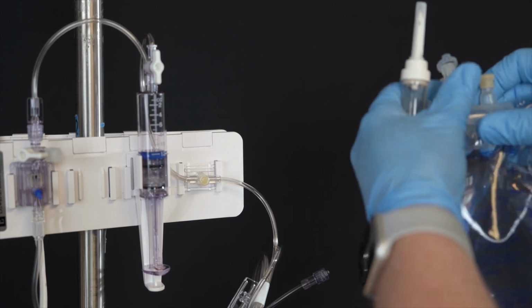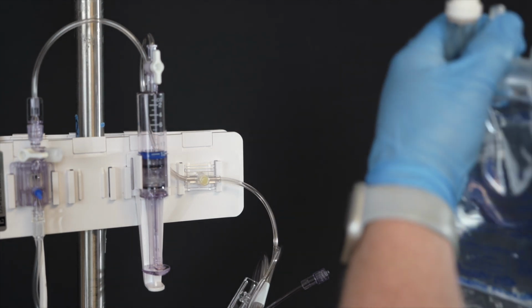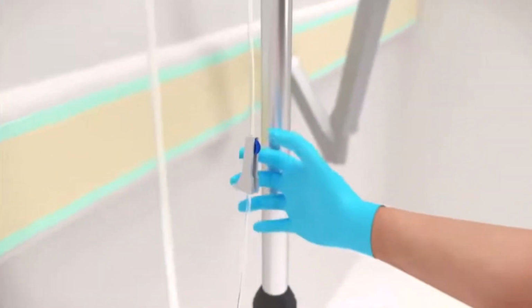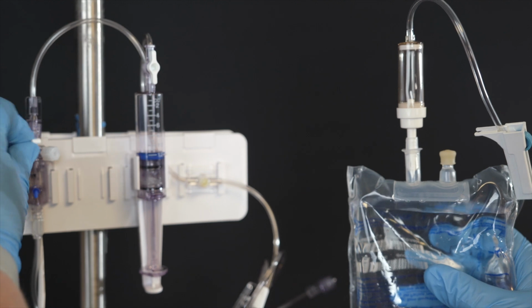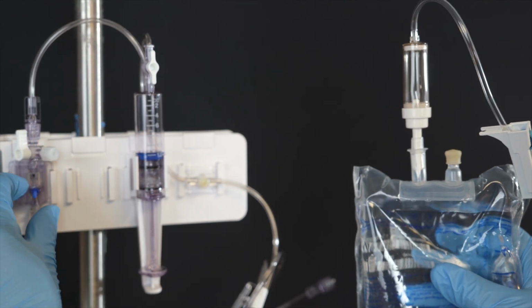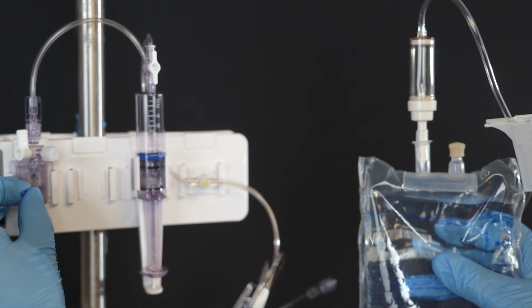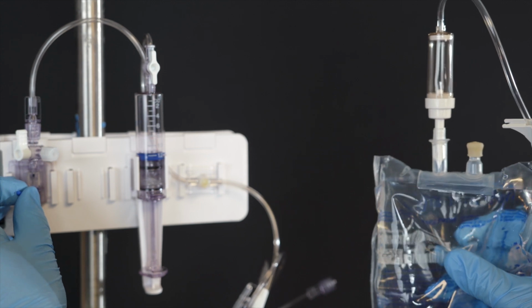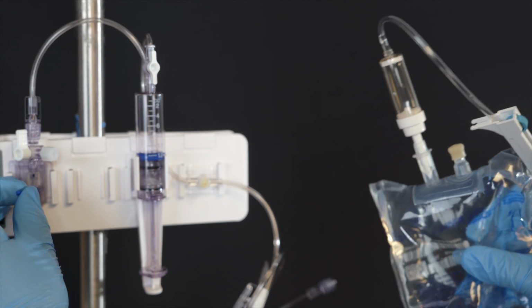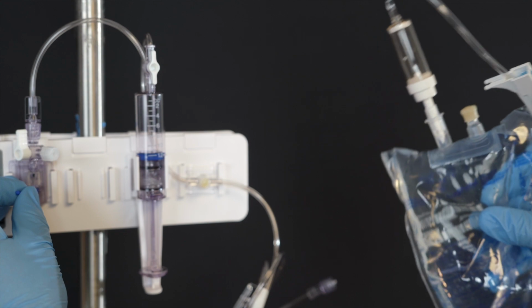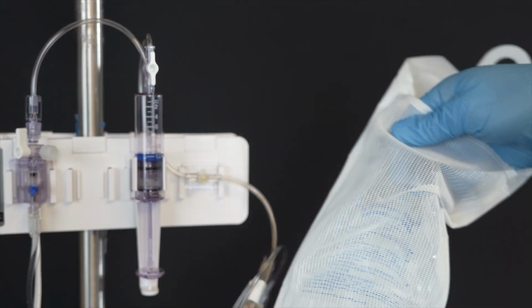Next, you'll need to de-air the IV bag and prime the TrueWave system. Spike the IV bag with the fluid administration set. Open the roller clamp on the IV set. Open the vent port by turning the stopcock toward the patient's pressure tubing. While keeping the IV bag inverted, gently squeeze air out of the bag while pulling the snap tab flush device until air is removed from the IV bag and drip chamber is filled about halfway.